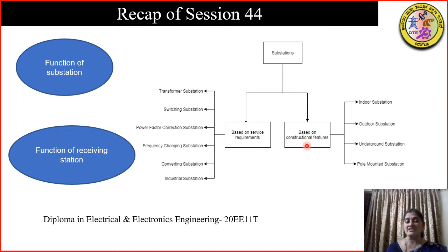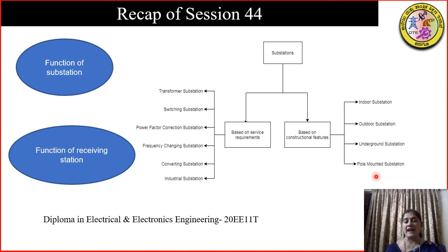Based on constructional features, we had four subdivisions: indoor substation, which was installed indoors for voltages below 66 kV; beyond 66 kV, we installed the substation outdoors. When there was a lack of space or high cost of land, we went into underground substation. The most popularly used substation as a distribution substation is the pole-mounted type, for convenience and saving on cost.